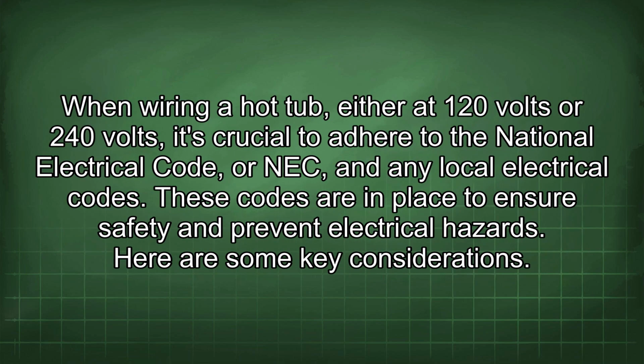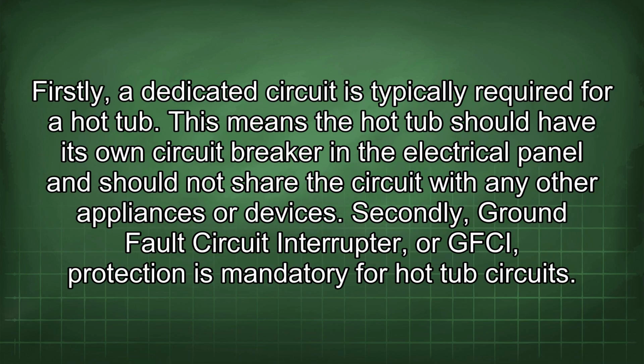When wiring a hot tub, either at 120 volts or 240 volts, it's crucial to adhere to the National Electrical Code, or NEC, and any local electrical codes. These codes are in place to ensure safety and prevent electrical hazards. Here are some key considerations. Firstly, a dedicated circuit is typically required for a hot tub. This means the hot tub should have its own circuit breaker in the electrical panel and should not share the circuit with any other appliances or devices.